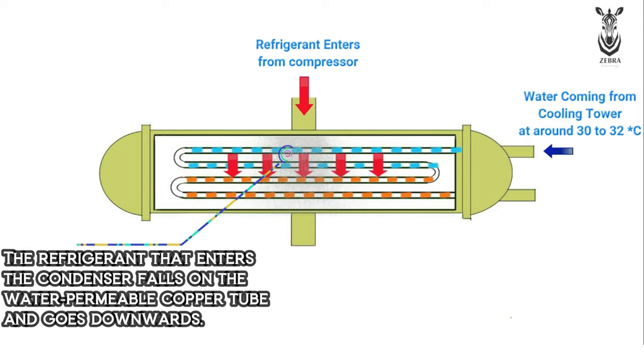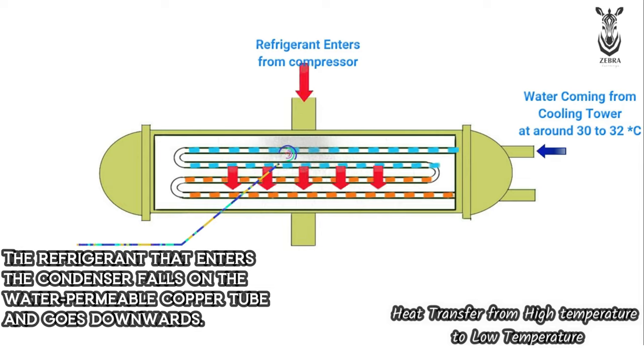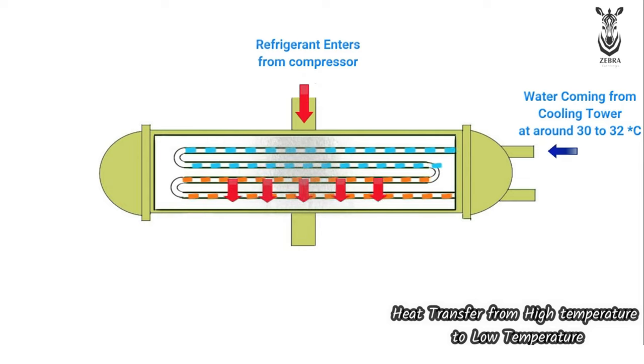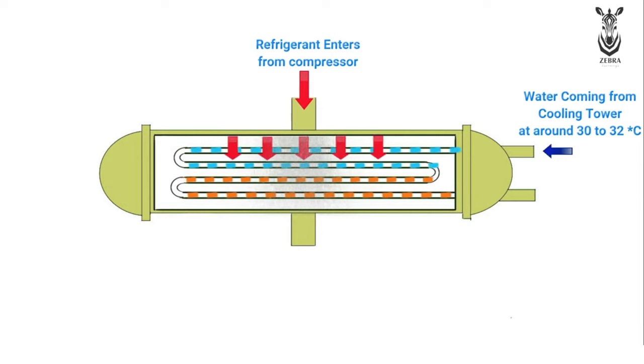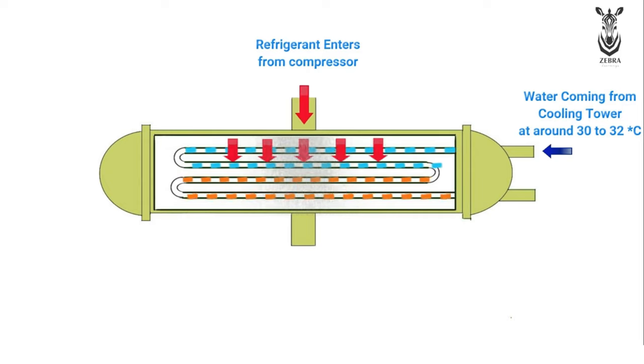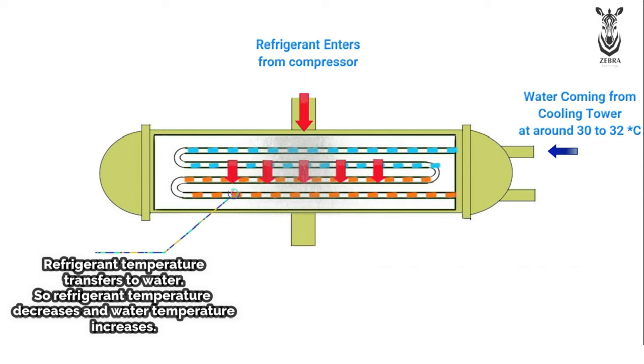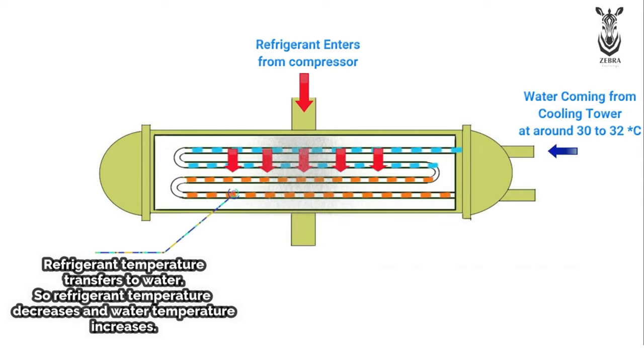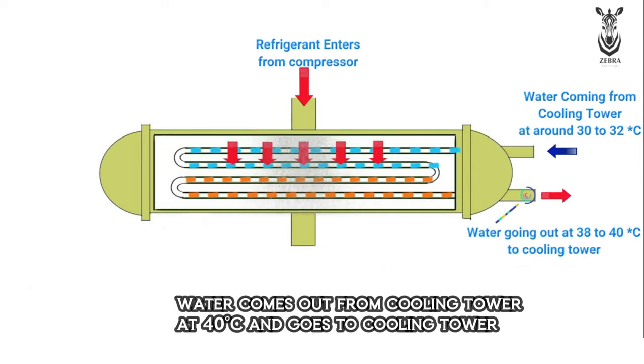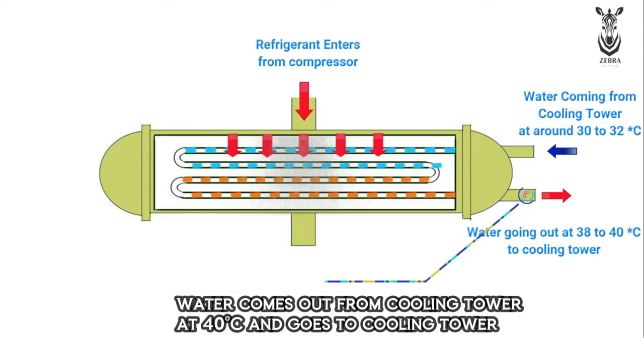As per the thermodynamics law, high temperature travels towards low temperature. So, the heat of the refrigerant which flows around the copper coil will transfer to the water which flows inside the copper coils, because the refrigerant temperature is higher than the water temperature. So the water temperature will increase, and the water comes out from the condenser at 40 degrees Celsius.